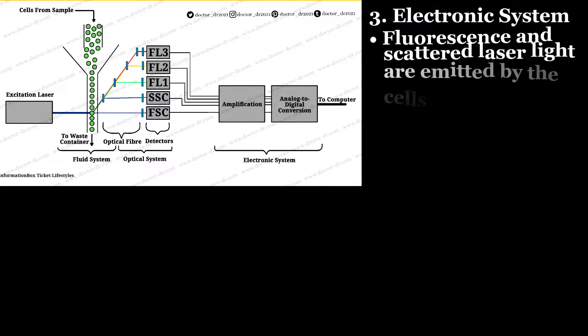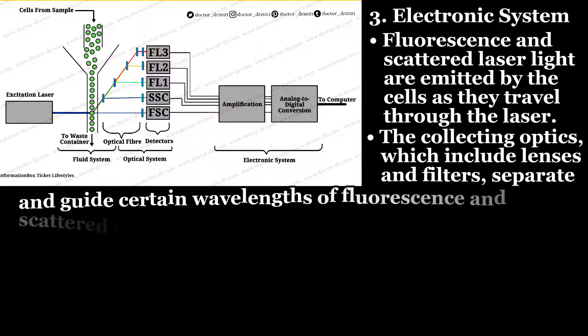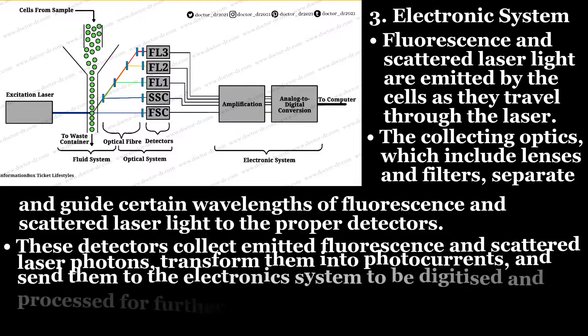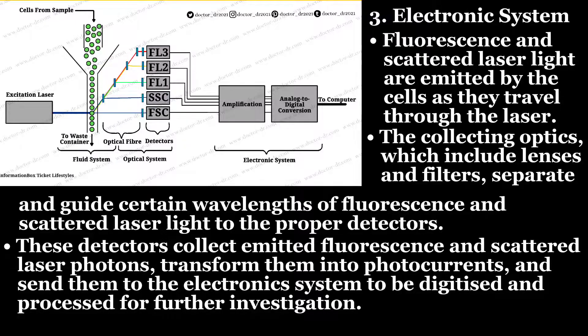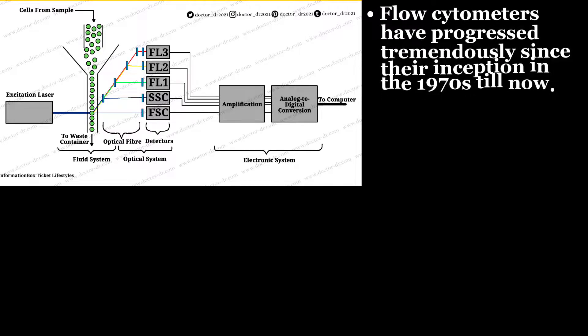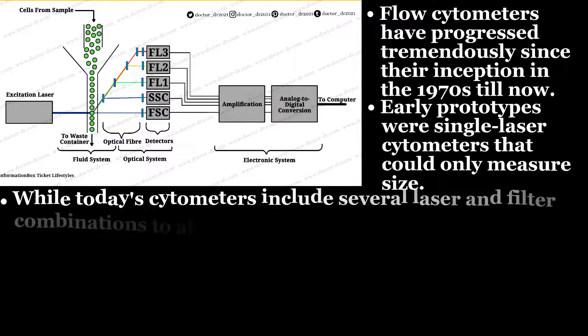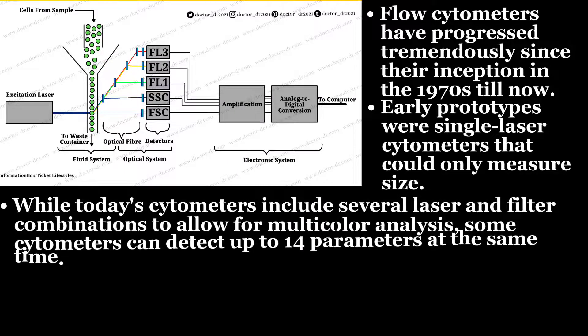Number three, the electronic system. As cells travel through the laser, fluorescence and scattered laser light are emitted. The collecting optics, which include lenses and filters, separate and guide certain wavelengths of fluorescence and scattered laser light to the proper detectors. These detectors collect emitted fluorescence and scattered laser photons, transform them into photocurrents, and send them to the electronic system to be digitalized and processed for further investigation. Flow cytometers have progressed tremendously since their inception in the 1970s — early prototypes were single-laser cytometers that could only measure size, while today's cytometers include several laser and filter combinations to allow for multicolor analysis.